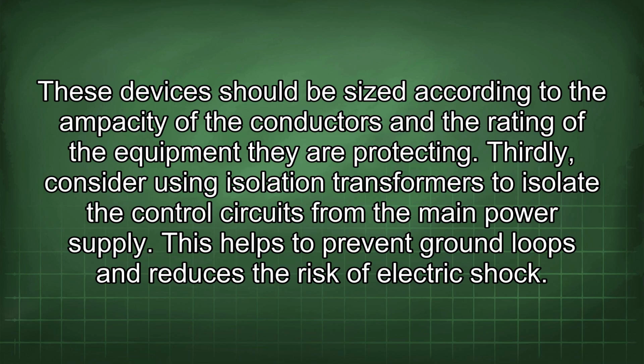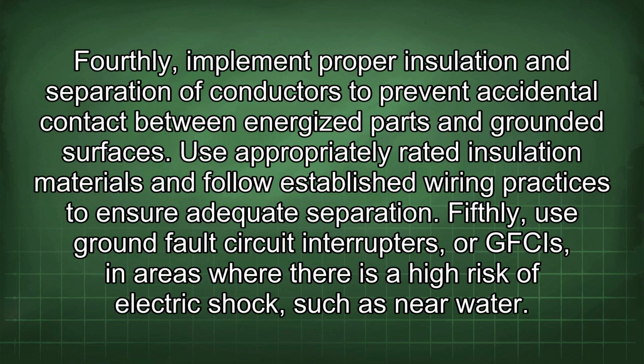protecting. Thirdly, consider using isolation transformers to isolate the control circuits from the main power supply. This helps to prevent ground loops and reduces the risk of electric shock. Fourthly, implement proper insulation and separation of conductors to prevent accidental contact between energized parts and grounded surfaces. Use appropriately rated insulation materials and follow established wiring practices to ensure adequate separation.